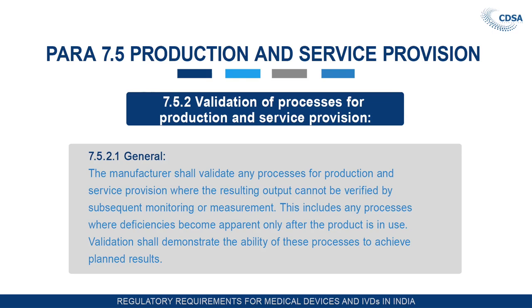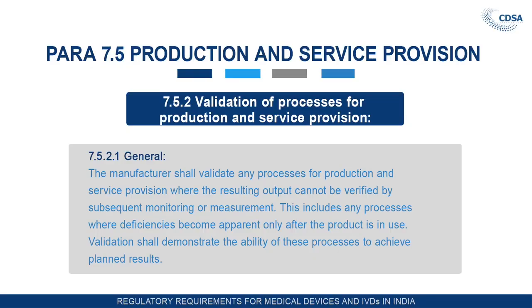There are a lot of medical devices. We know very well that there are medical devices where the usage of that product cannot be validated by way of end product testing at the end of the production cycle. So, in that case, the manufacturer has to validate each process that is going on in the manufacturing, which is of course designed carefully for that particular process, so that at the end of the day, even if the product is not tested, it complies with your standards.